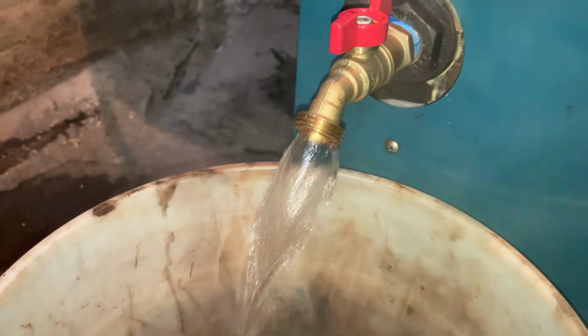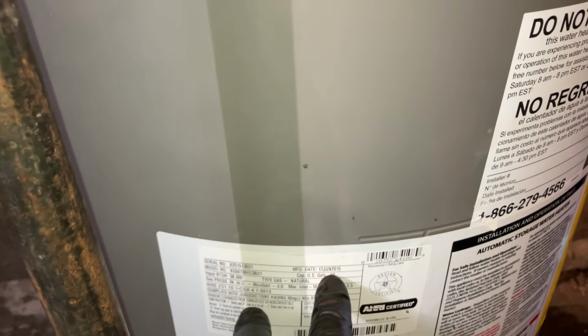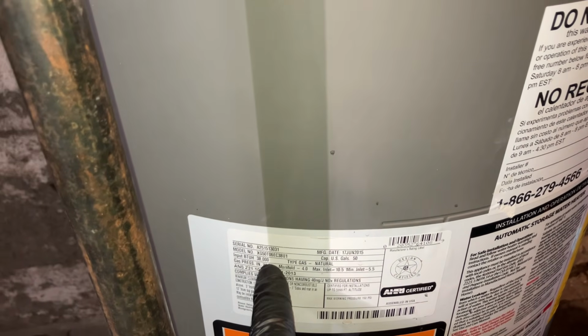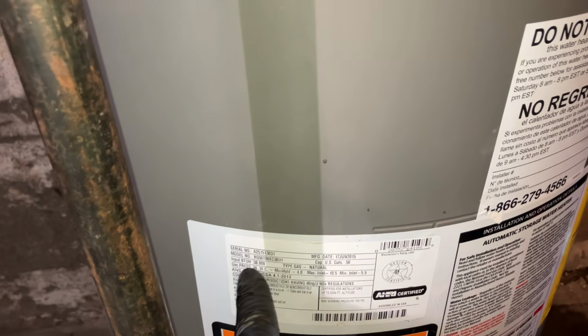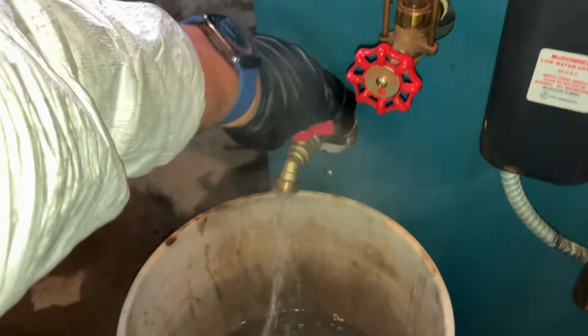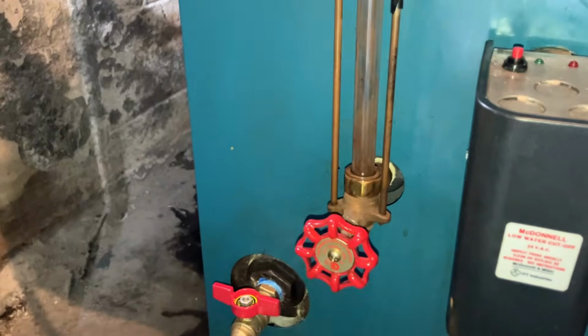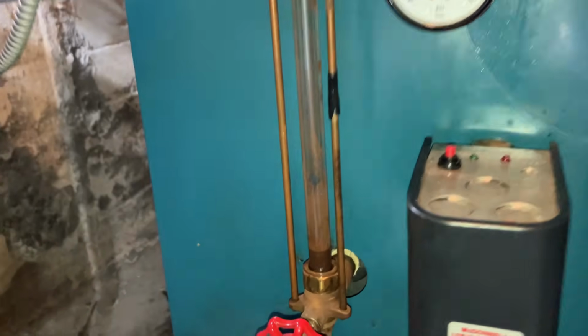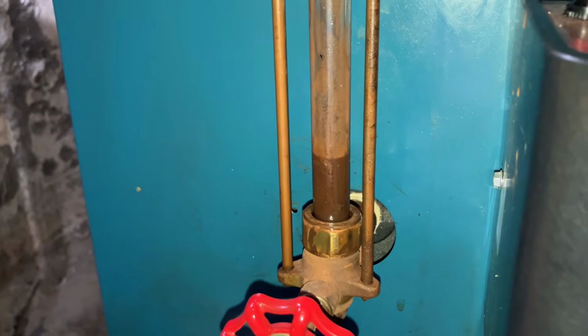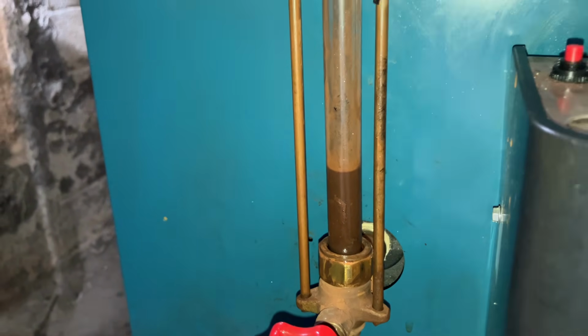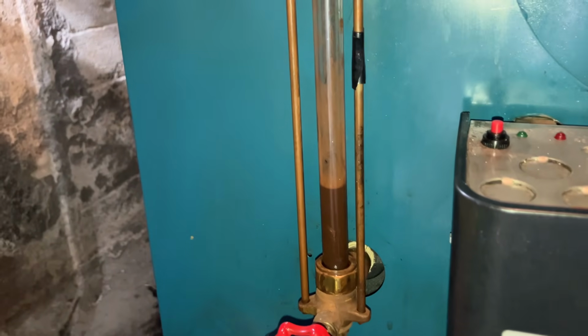All right, that water is fairly clean. Let's fill her back up, halfway up. Yeah, we got that percolating sound coming from this almost 10-year-old natural gas-fired water heater, 38,000 BTUs, which is 50 gallons. I don't know why it's not 40,000, but that's a Home Depot difference for you. Let's close that valve. Let's get this thing filled up about halfway, 5/8 or 3/4 full. We could be here for hours trying to drain and flush out the bottom of the boiler, but still better than what was before.